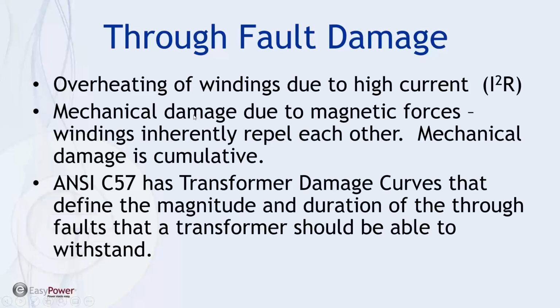It also prevents mechanical damage due to the magnetic forces, because windings inherently repel each other. And if we see a large surge of a fault, that large magnetic force could cause mechanical damage to the core or to the windings themselves. The ANSI standard C57.109 has been developed to define transformer damage curves and define the magnitude and duration of through faults that a transformer should be able to withstand.